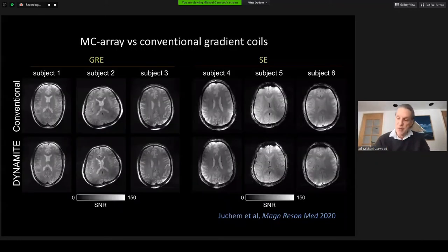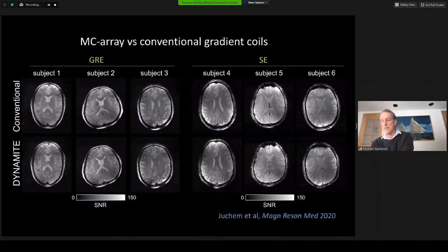Just recently, we showed that the MC array can be used instead of conventional gradients for imaging the human brain. Please note, these images were not acquired with the new head-only magnet, which is still under construction, but instead used the 4-Tesla magnet at Yale to demonstrate proof of principle. Gradient echo images are on the left and spin echo images are on the right. Note there is little difference between images acquired using conventional gradients, shown in the top row, versus the MC array in the bottom row.